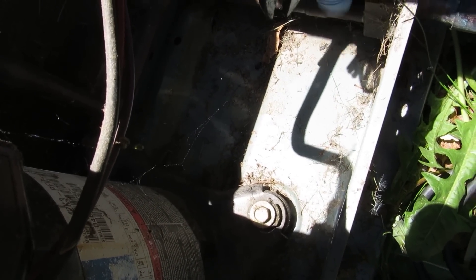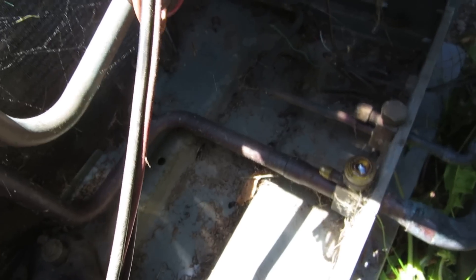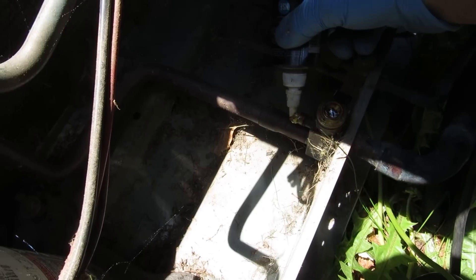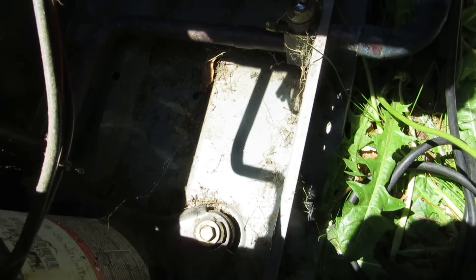The straight is leaking by. I got a leak upstairs - I found the leak. This is a Ruud unit. Must be leaking from that fitting somewhere, but that all looks good.